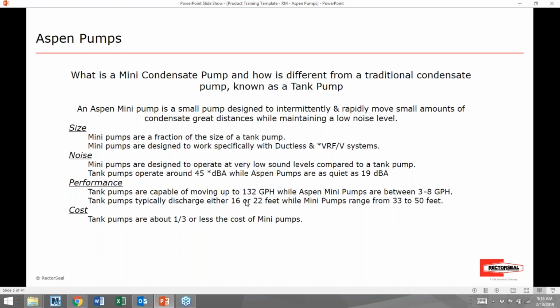And the first thing we need to be concerned with is size. Mini pumps are just a fraction of the size of a tank pump. Tank pump, think of the size of a shoebox, whereas a mini pump might be 6 inches long and 2 inches by 2 inches wide and tall. The other consideration is that mini pumps' size is designed to work specifically with ductless and VRF systems. Oftentimes there's not a lot of room inside the back of a high wall unit where many times we'll place a pump, so it does have to be small and slender to fit those tight spaces.